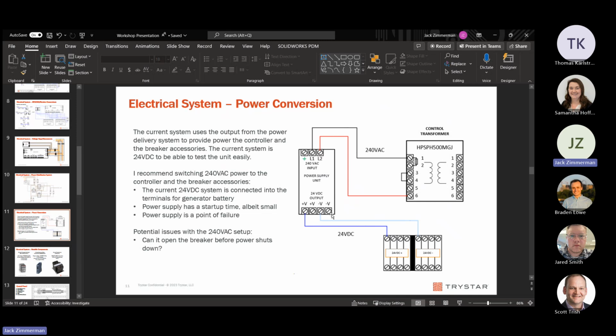And like I said, none of this invalidates the 24 volt unit for being a commercially viable unit that works. It's just that when we look at some kind of failure mode analysis, this would be one of the things to look at, as in, hey, we should maybe consider running 240 volt AC. But there is a question with the 240 volt AC system: when your power shuts down from utility and you need your generator to come up, can it open the breaker for your utility power fast enough before it shuts down? With the power supply, it can, because you have some capacitor time delay.